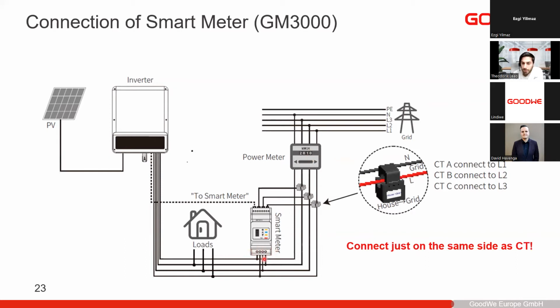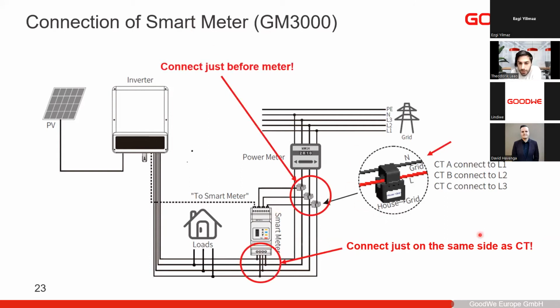Likewise, on the bottom side here of the smart meter, you have 4 cables, and these are the voltage sense to check the voltage in the lines, and these also need to be connected at the same point as the CTs. They should have the same voltage as the CTs, as the voltage where the CTs are measuring. Otherwise, you might get some different and weird values. In some cases, I've seen people connecting it on the other side of the loads here. So you have some load in between, but then you will have a voltage drop and the voltage that's read from the smart meter will not be true. So make sure that you connect them as close as possible to the CTs. And you see that you have 4 here, so 1 is also for neutral. I think there's 1, yeah, exactly, just before the meter, and connect just on the same side as the CTs.